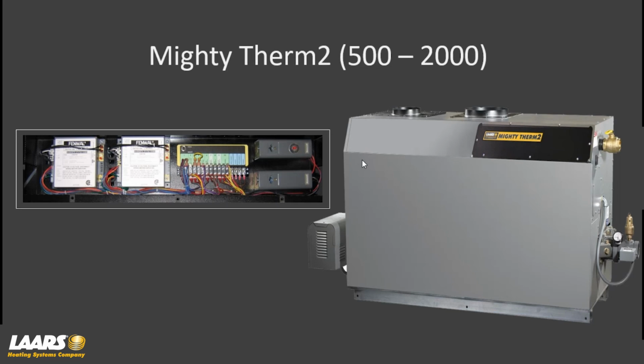The MightyTherm2, we'll go through this first, and we'll go through troubleshooting on the MightyTherm2, and then get into the Pennant. So the MightyTherm2, again, weather-tight cover. This cover plate here is also weather-tight. You would remove the cover, and this is the control system that you would see. Very simple point-to-point wiring. Use a voltmeter to identify your safety chain that's open. We'll go through that. Up to 2 ignition controls. So if you have a product of 1250 or 2 million BTUs, you can have 2 blowers, 2 ignition controls. Your smaller sizes, such as a 500 or 750,000 BTUs, will only have a single ignition control.